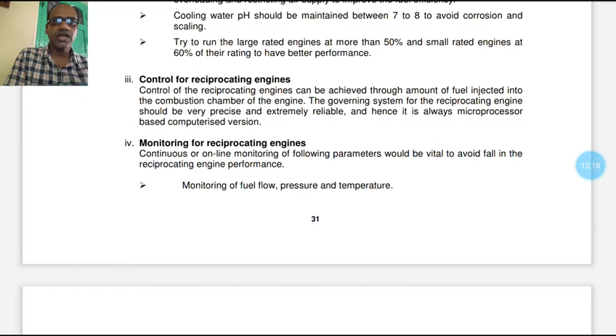Monitoring of reciprocating engine. Continuous or online monitoring of the following parameters would be vital to avoid a fall in the reciprocating engine performance. Monitoring of fuel flow, pressure and temperature. Monitoring of exhaust flue gas temperature is a must in order to monitor the performance of the waste heat recovery system. Monitoring of bearing vibration of engine and generator must be carried out using suitable microprocessor based instrumentation. Monitoring of pressure and temperature of lube oil sent to engine cylinder and crankshaft bearing lubrication is important.